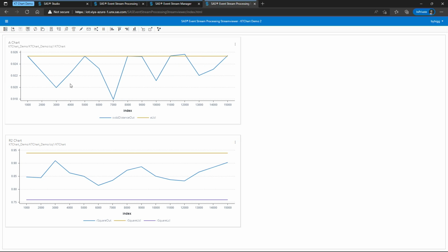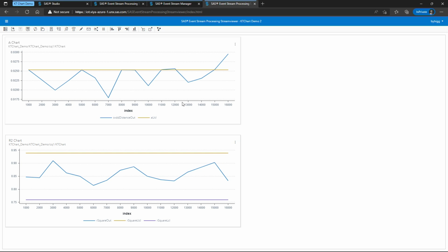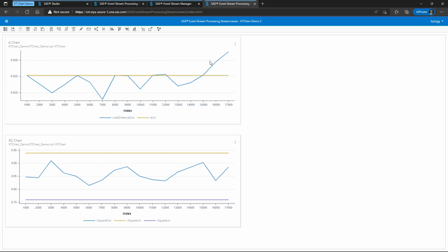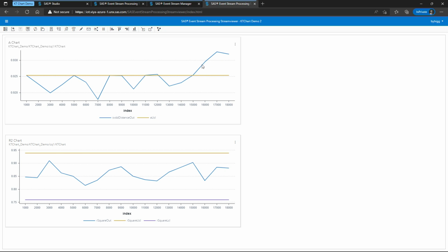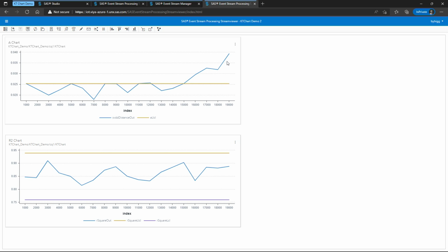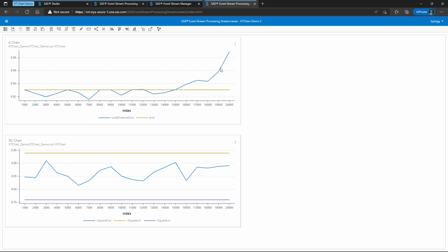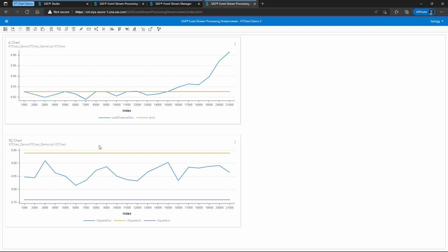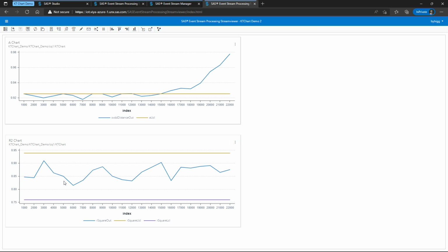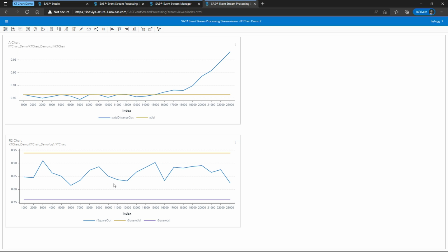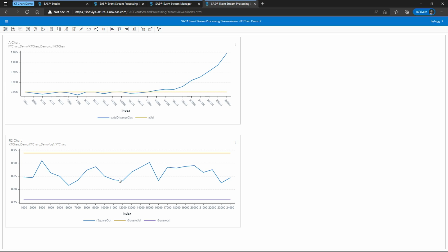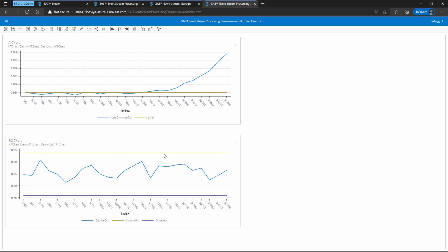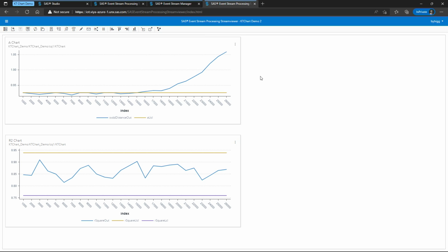And we see at the beginning we're within the control limits essentially, and as time progresses, we see the center is drifting away, going above the upper control limit. And this indicates that we've identified a fault. At the bottom, again, as we saw in the KT monitor output, we see that the spread is remaining within the upper and lower control limits pretty well, but the center is pretty clearly drifting outside.